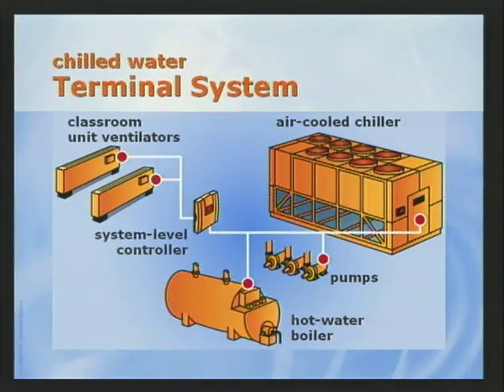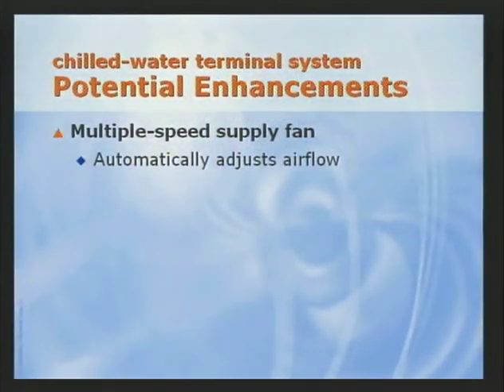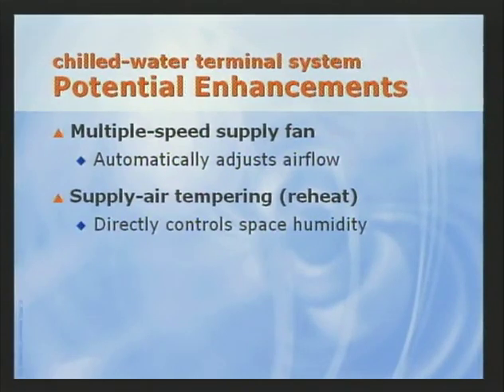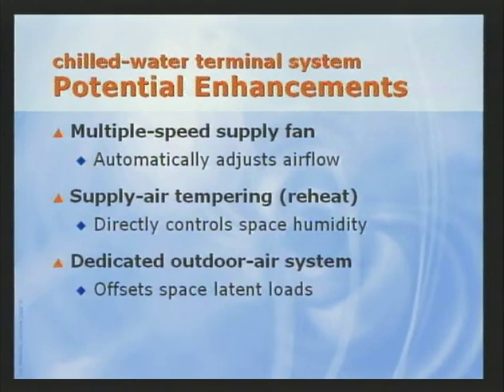Now, a chilled water terminal system uses a central cooling plant to distribute chilled water to terminal units that are located in or near each classroom. Each terminal unit is a basic single-zone constant volume system that contains a fan and a cooling coil. Examples of equipment in this category may include classroom unit ventilators, fan coils, or blower coils. Now we'll look at three methods commonly used to improve the part load dehumidification performance of this type of system. The first is a multiple speed supply fan with a controller that automatically steps down fan speed at part load. The next is direct control of space humidity by overcooling and tempering or reheating the supply air. The third is a dedicated outdoor air system that dehumidifies all of the incoming ventilation air and then delivers it dry enough to also offset the space latent loads.